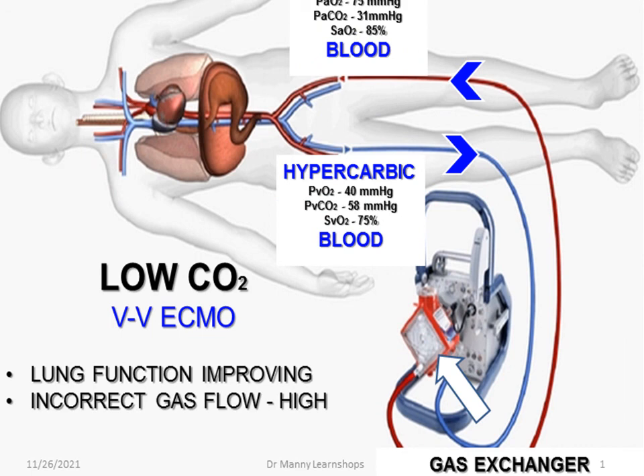Low CO2. This can be a sign that you've got an incorrect gas flow, as I mentioned. You've got too much gas flow going into the gas exchanger, which is increasing CO2 removal. Yes, increasing oxygen delivery, which is good. Or it could actually be a sign that your lung function is improving.